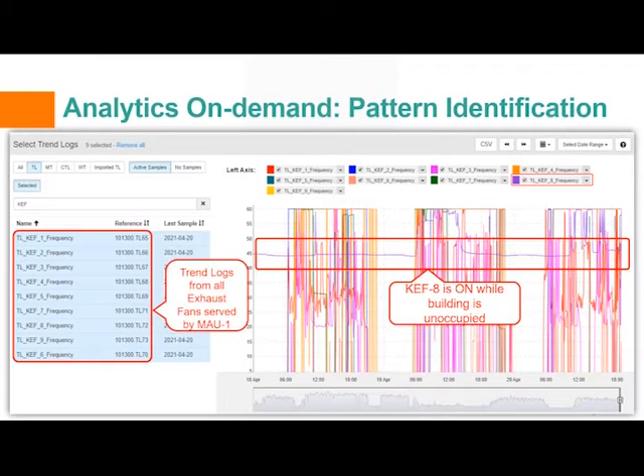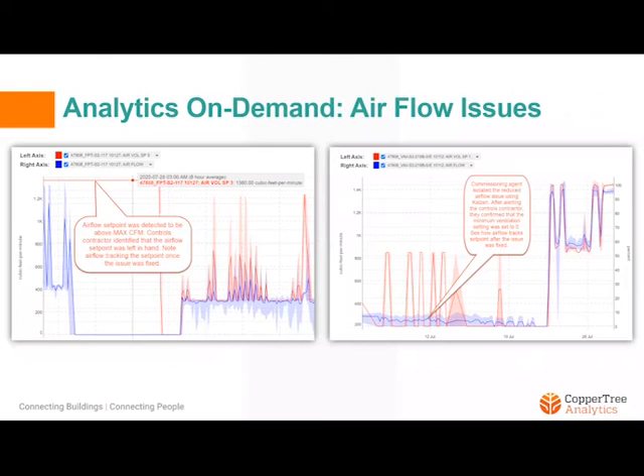To validate this, we can simply select a date range when MAU1 was operating as per the time of day schedule and confirm that kitchen exhaust fan 8 was also being disabled. Let's move on to another example.